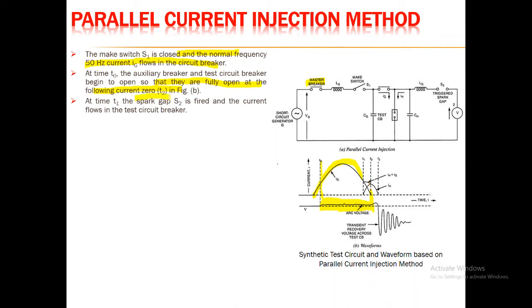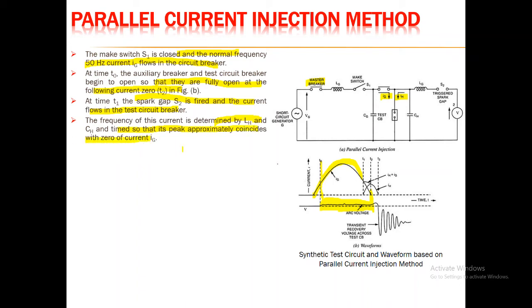At time T1, the spark gap S2 is triggered and the current flows in the test circuit breaker, which is the combination of IG and IH. The frequency of this combined current is determined by LH and CH, and the timing is such that its peak approximately coincides with the zero of IG. As seen in the waveform, at instant T1 the spark gap is triggered, resulting in the total current through the circuit breaker under test being IG plus IH.